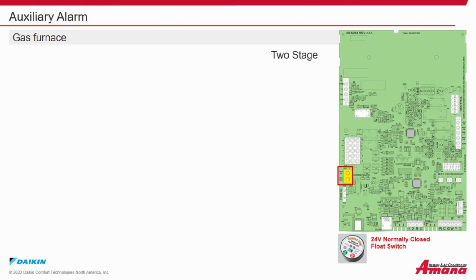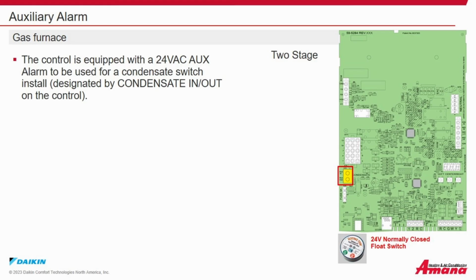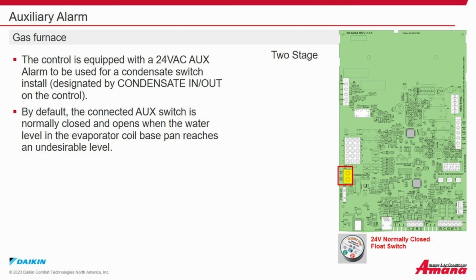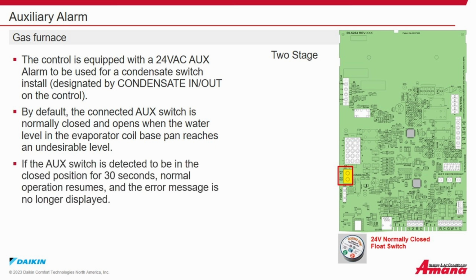On gas furnaces, the control is equipped with a 24-volt AC auxiliary alarm to be used for a condensate switch install designated by condensate in-out on the control. By default, the connected auxiliary switch is normally closed and opens when the water level in the evaporator coil pan reaches an undesirable level. If the auxiliary switch is detected to be in the closed position for 30 seconds, normal operation resumes, and the error message is no longer displayed.